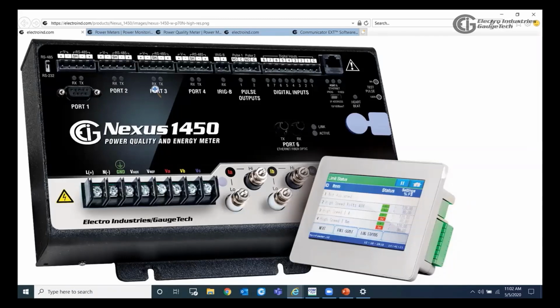It has multi-communication ports. As you can see here, it has 4 serial communication ports. The first one can be switched between an RS-232 and RS-485, and the other 3 serial ports are RS-485 ports. It has also port 5, which is an Ethernet RJ45 normal copper connector, and port 6, which is the Ethernet fiber optic port. So this meter can have 2 separate IP addresses at these 2 ports.